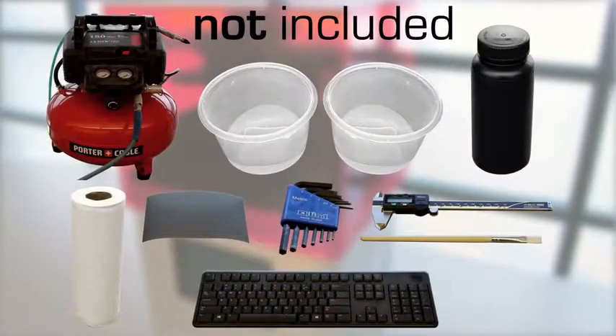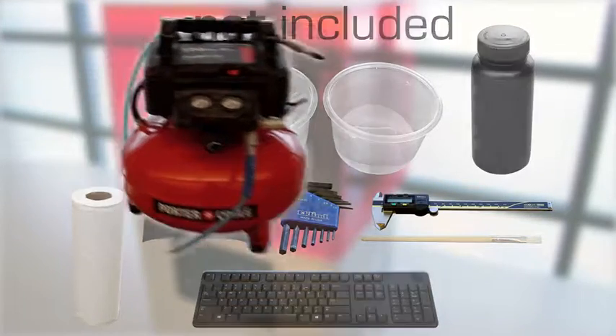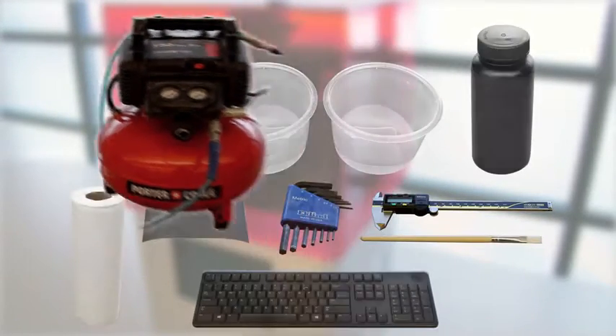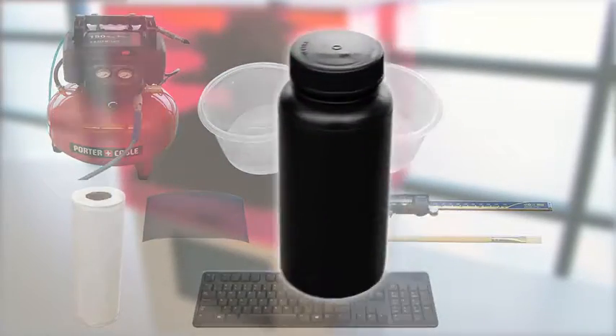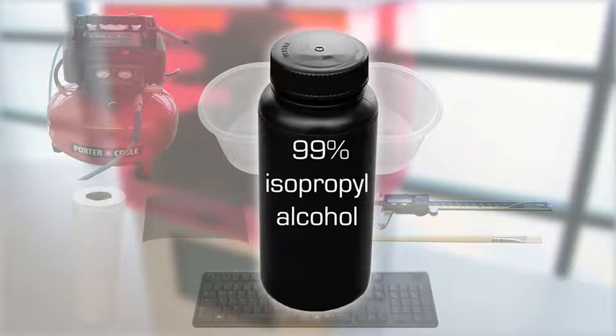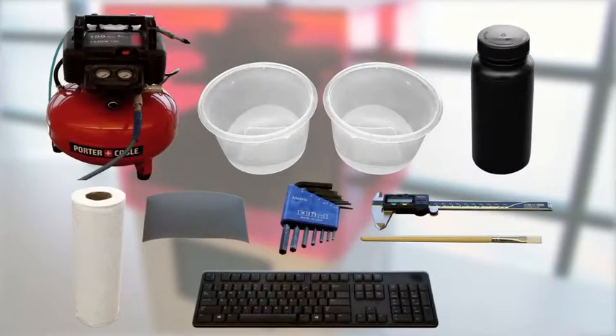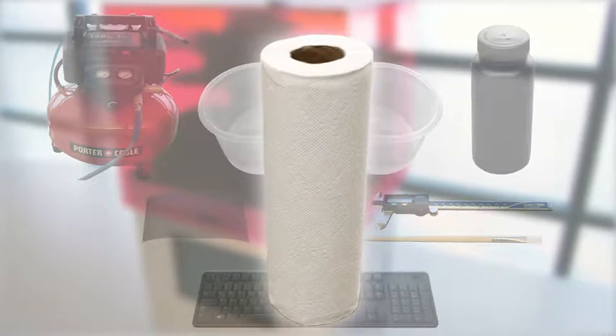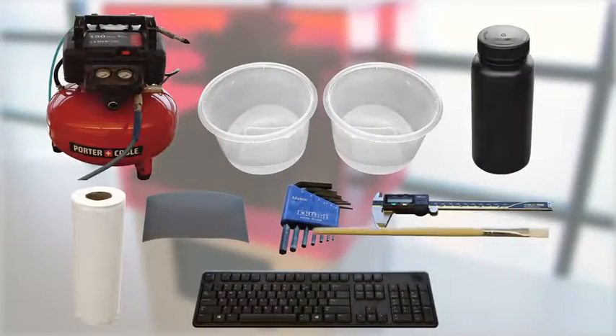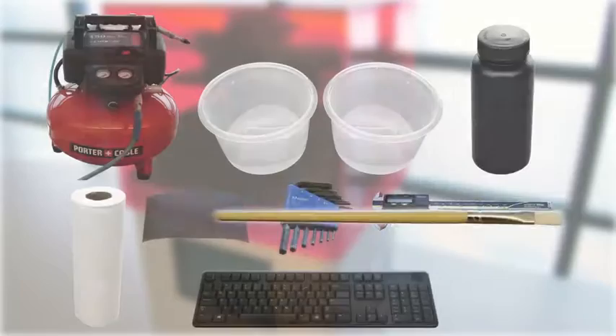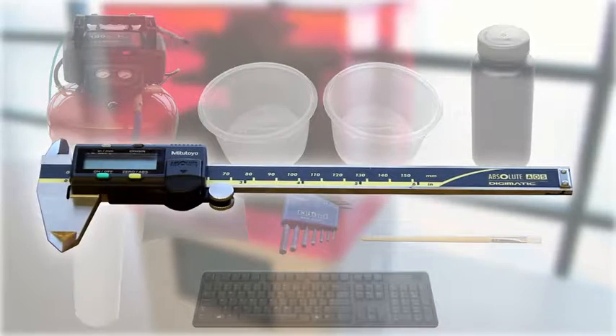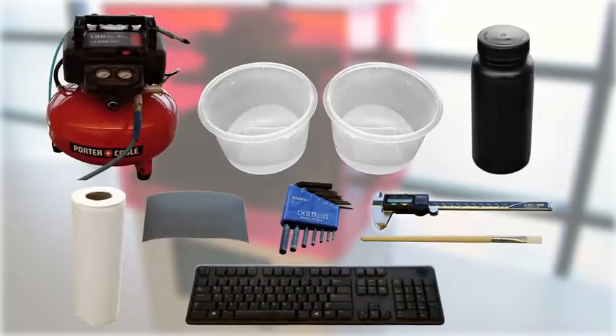The things you will need that do not come with the machine are an air compressor, 2 plastic containers with lids, 99% isopropyl alcohol, or 91% if you can only get it from your local drugstore, a roll of paper towels that are absorbent, a set of Allen wrenches, one paintbrush used in the cleaning process, gray mylar film that we use for focusing, digital calipers for measuring, a keyboard and/or mouse.